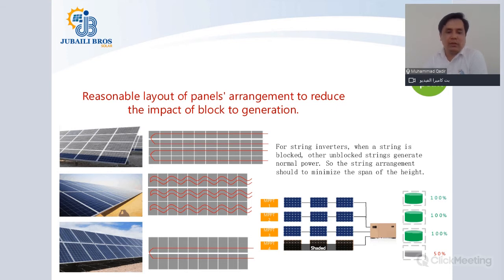So this is a scenario as shown in this small SLD in the picture. You can see that the solar panel and the MPPT4 are shaded, and since the MPPTs are independent from each other, only the MPPT4 is affected, which might produce around 50%, but the first three MPPTs of this inverter are producing 100%, because they are not affected by the shade on the MPPT4.